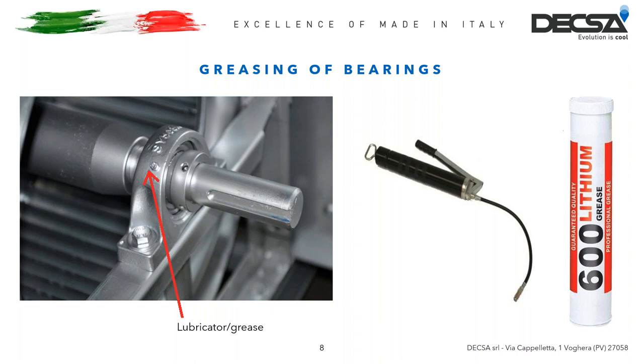Now we can proceed to greasing the bearings — remember, every four months or 3,000 hours of operation. Above each support there is a lubricator to which the pump nozzle must be connected. Here is the lubricator, here is the nozzle, and this is the pump to do this job. This pump must contain a lithium grease cartridge for bearings. The quantity of grease to be used corresponds to three pump strokes — just to understand the quantity, think of a soup spoon. After this operation, you must rotate the transmission manually for even distribution.